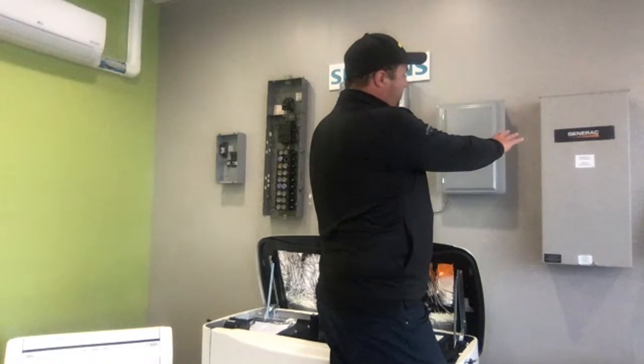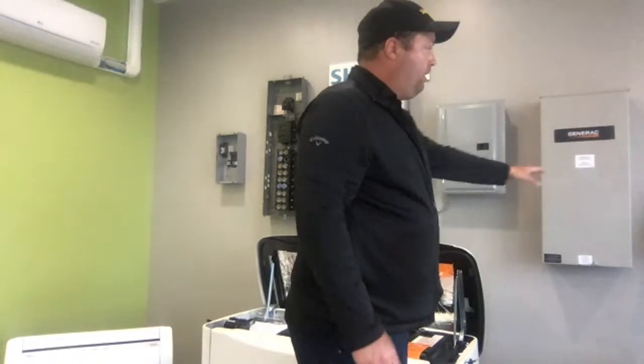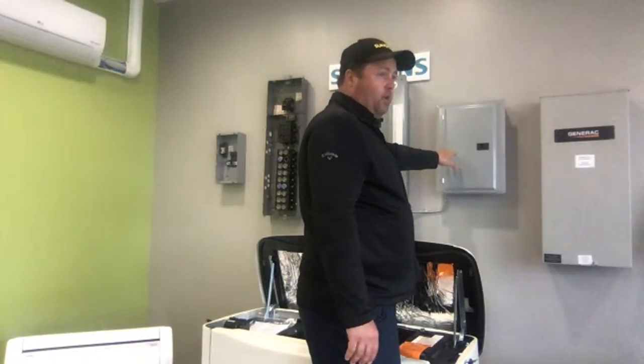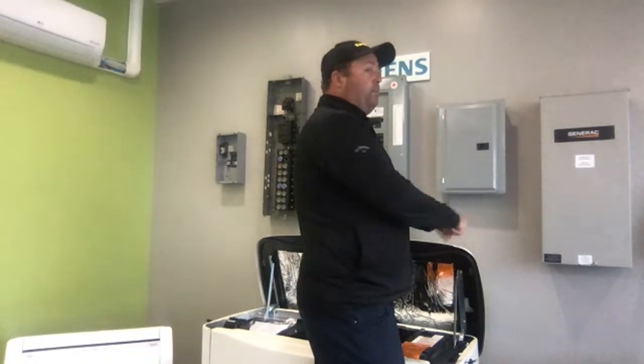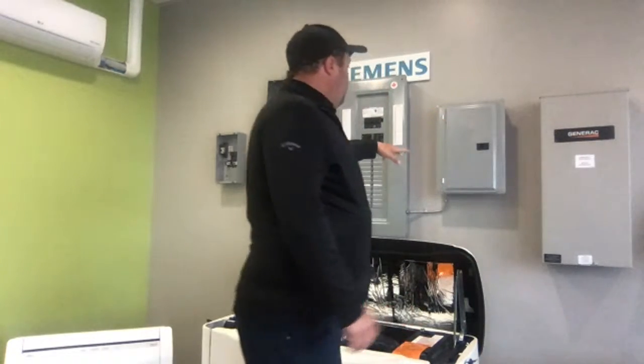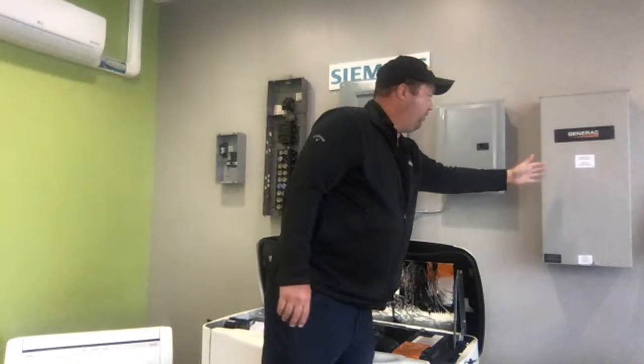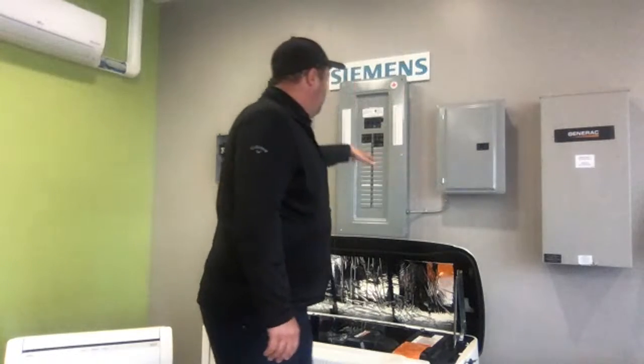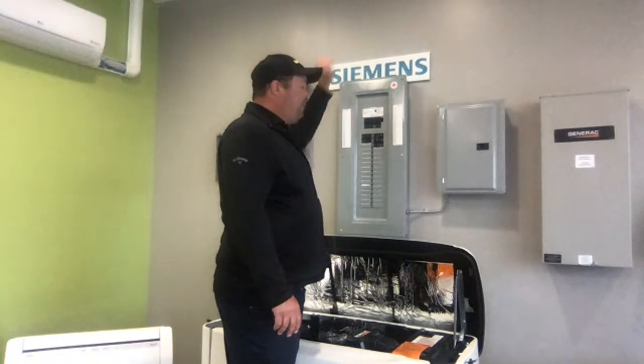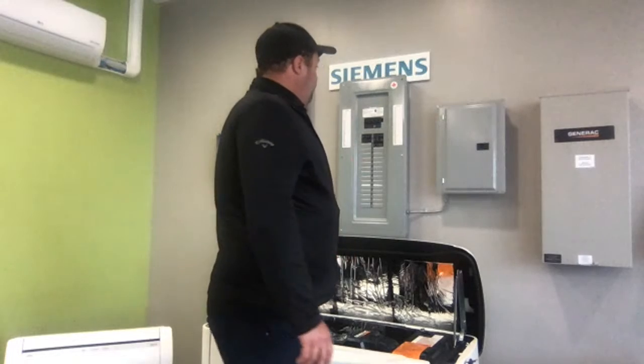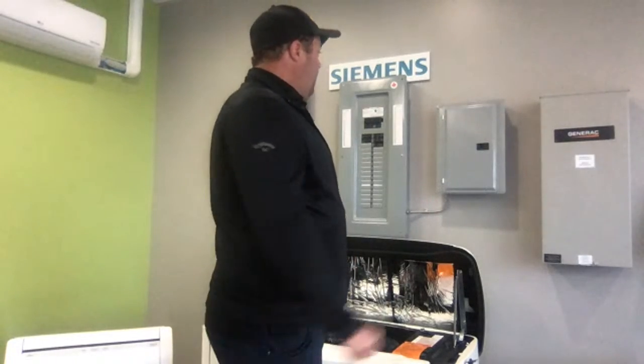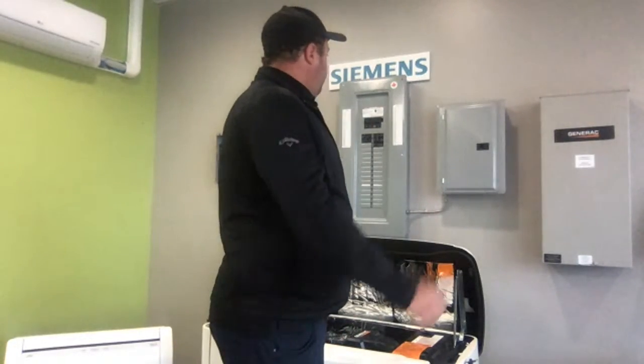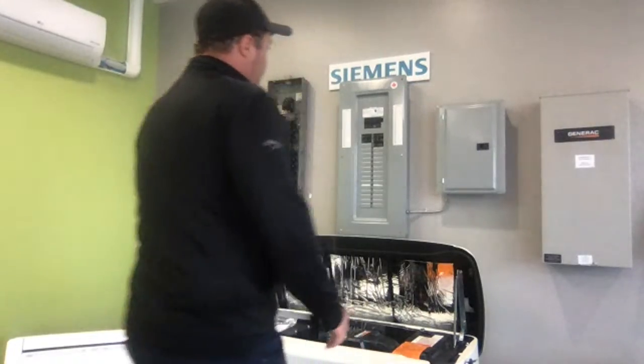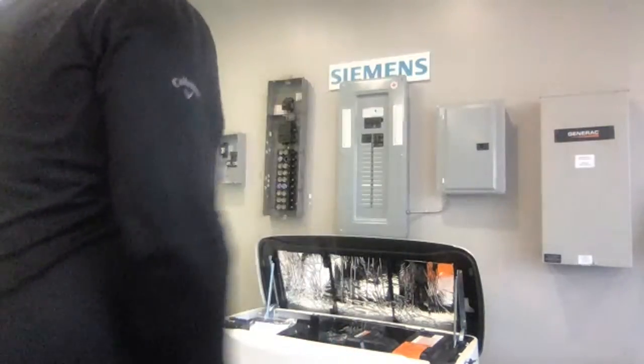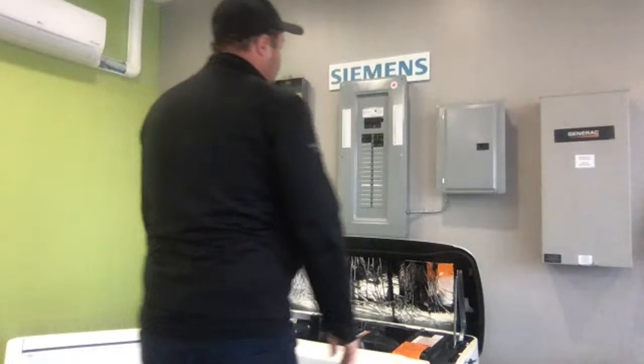They both operate the same kind of way. This one's done automatically. This one's done by actually turning on your generator and plugging it in. Essentially, these 2 panels isolate themselves from the main panel so that you're not backfeeding the grid. Back in the day, people would just plug into their dryer outlet, start up the generator, and juice the lines, then a lineman comes out, touches the cable, gets lit up, and they're not happy.